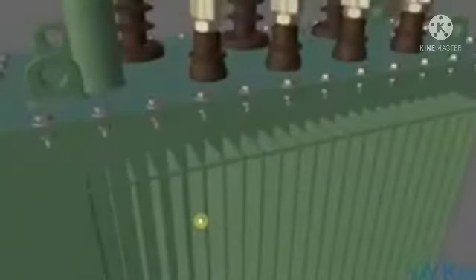What's actually going to happen is that some of the insulating liquid is going to absorb the heat generated by the transformer, and it's going to pass that heat on to the fins, and the fins are going to pass the heat on to the air. So the reason for the fins is to increase the contact surface area between the tank and the air, and this means we're going to get a much higher heat transfer rate. If we can keep the transformer cool, then we can also load it more heavily, at least up to a point. It's important to realise that if you can keep the transformer cool, then you'll also extend its useful working life. Overheating is typically one of the big killers of transformers.